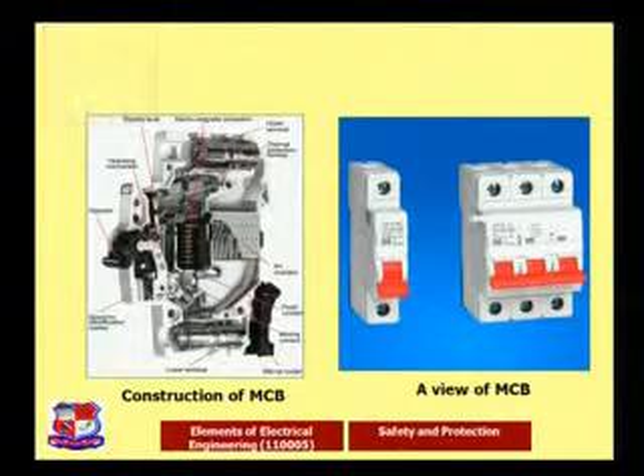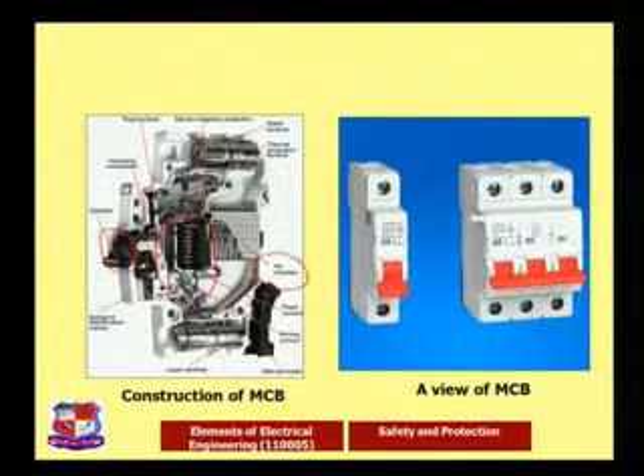Construction of the MCB. This is simple. The on-off switch is there. The arc chamber, where the contacts are in the open condition and the arc is going to be there, and this is the solenoid mechanism, where the electromagnetic protection is going to be there. So this we can say is some spring type, or technically we call it the plunger type, where the plunger is going to strike and release the latch mechanism. Normally when the circuit is closed, it is in the on condition, but as soon as the plunger strikes, it will come back into the off position.